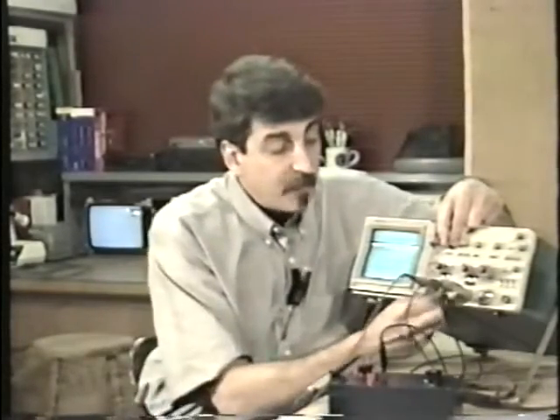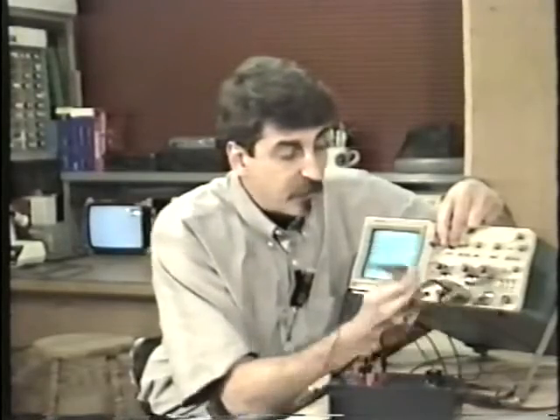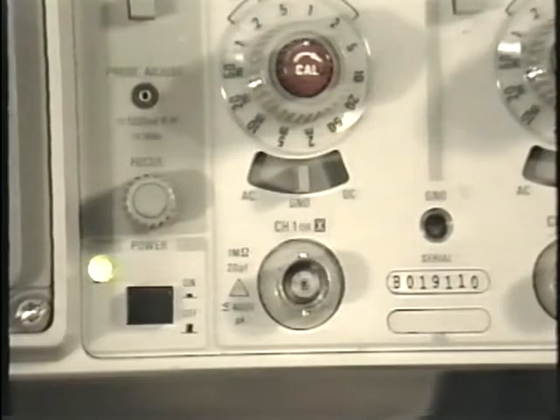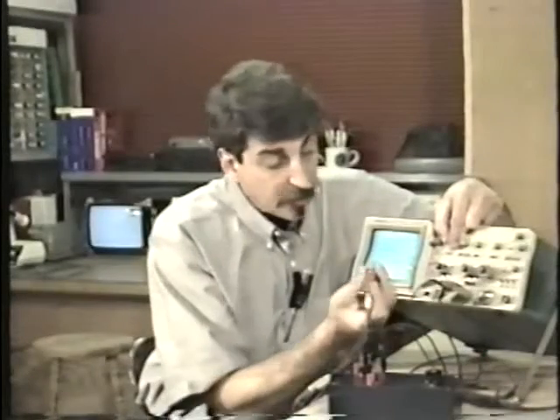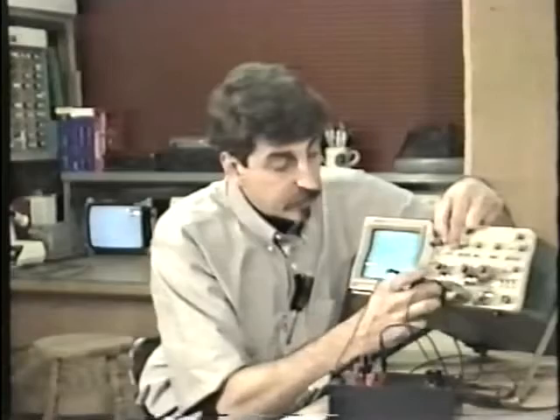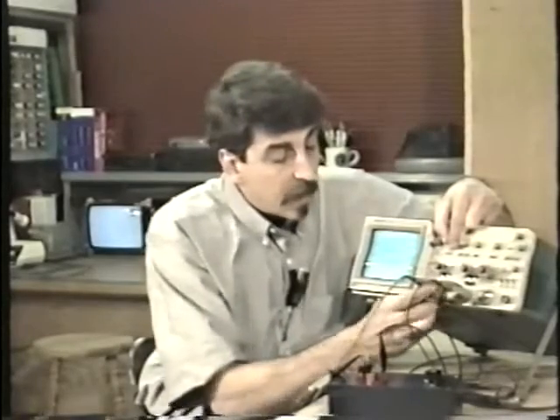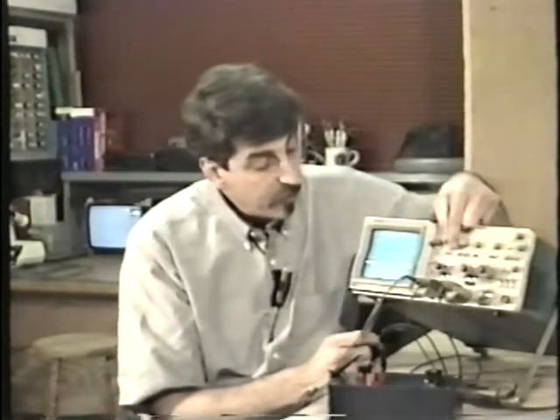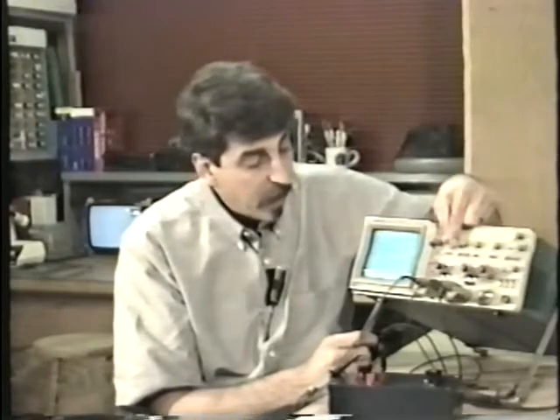Of course, now it's all out of calibration, and I have to recalibrate the baseline. And I do that by setting the input selector here to ground and selecting a new spot for my baseline. You don't actually have to remove the probe. I just did that so you can see the selector here. Now, we have a couple of choices. We can either move the baseline way down to the bottom and stay on 2 volts per division. Let's see how that works. And here we see, again, here's the baseline, the first line up from the bottom.